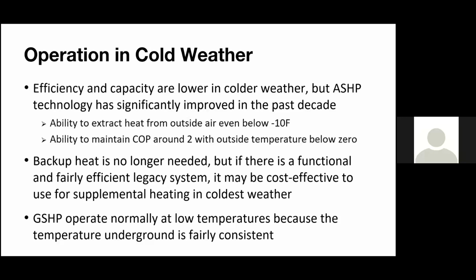It's more of a preference if needed. And then if we have low temperatures, we're designing up in Maine or something like that, ground source heat pumps could be an option. As we mentioned, they are a fairly constant temperature. You might have 40 degrees, and that is a lot more predictable than the air changing in the wintertime. So if you do want to look into ground source heat pumps, that's not a bad option. The only thing I would say is, initially there is a much higher cost for installation, and you do need to have an engineering team heavily involved in the process early on as you look at this type of approach.